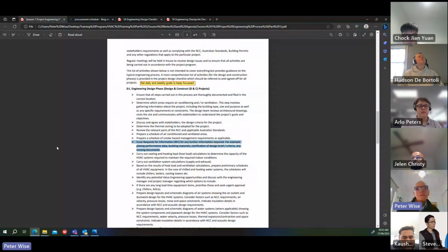For example, when doing design you might need glazing performance data. This is probably the first thing you'll find—nobody seems to know what glass they're using. If a consultant designed for certain glass performance data, U value and shading coefficient, that might change—somebody might decide to change the glass to save a million dollars. But what effect does that have on the design? It has a huge effect, so you need to get that confirmed.